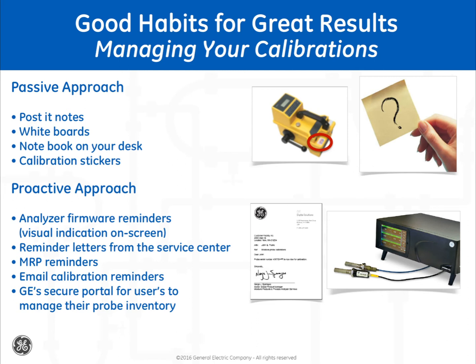More can be done. The vendor may choose to send out calibration reminder letters from their service center. This requires accurate installed base information correlated to the product's calibration dates. These letters nicely complement the various offerings, as the vendor now has a relationship with the sensor's technician. MRP systems such as SAP and Oracle and other software programs can provide reminders. When the customer has this capability, even though it is on their own, it typically ensures regular calibrations. GE provides a secure portal where the user can assign their sensors to their plant and get email calibration reminders. With the instrument calibration portal, the user dictates how often the calibration is required based on measurement criticality. This is ideal for smaller companies that do not have expensive software systems.